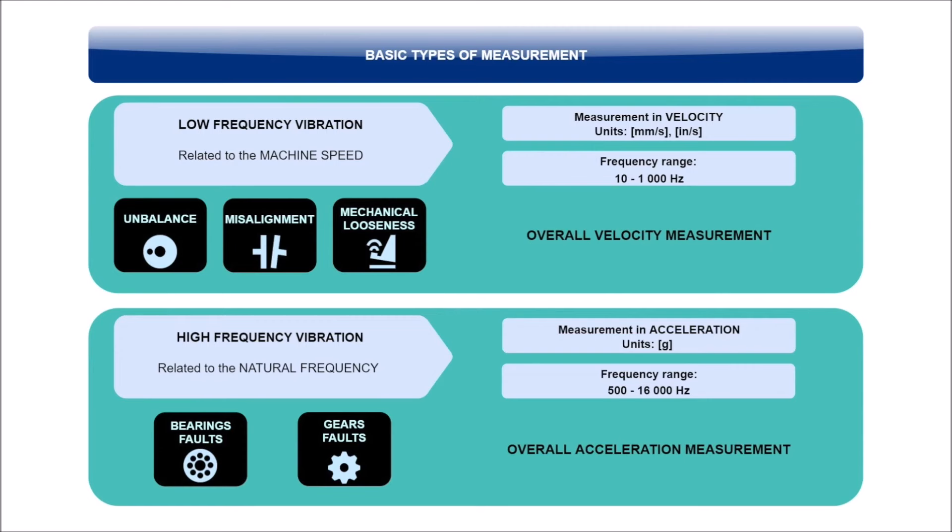So, for quick summarization, there are two important values which we should measure regularly on our machines. Overall velocity in millimeters per second, or inches per second, the lower frequency range, which indicates the general machine condition. Overall acceleration in G, the higher frequency range, which indicates the bearing condition.